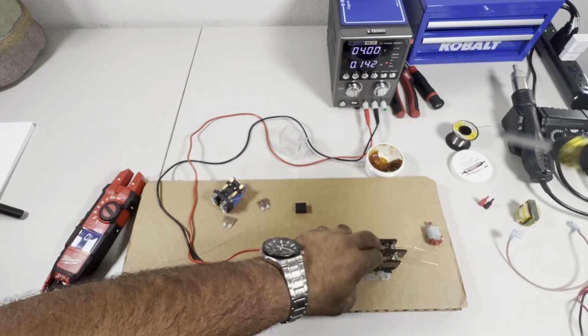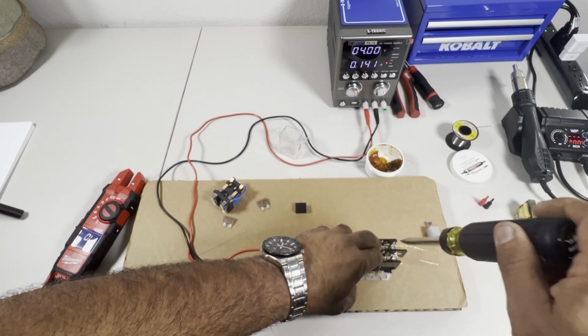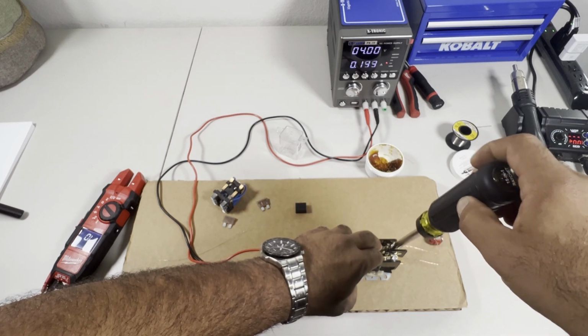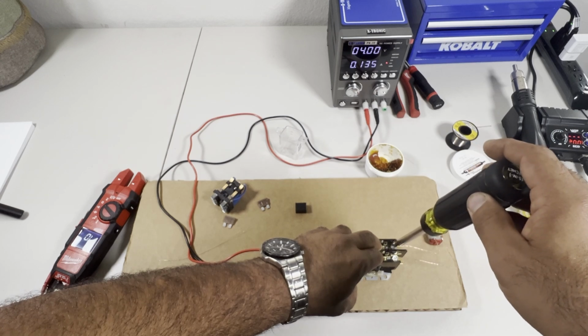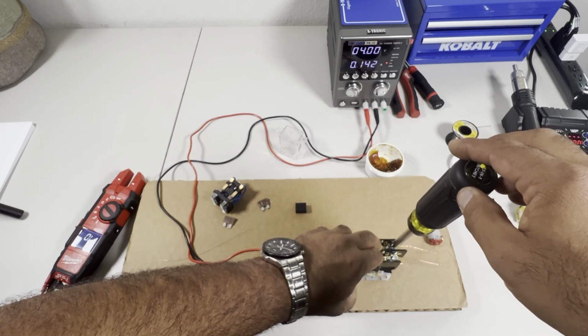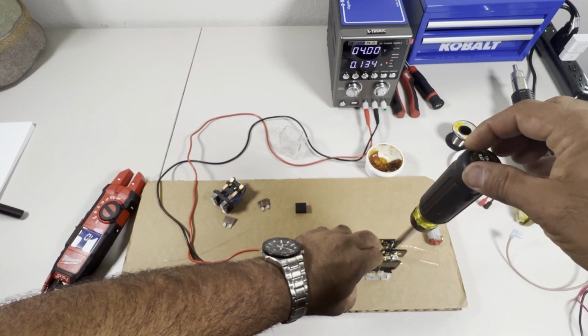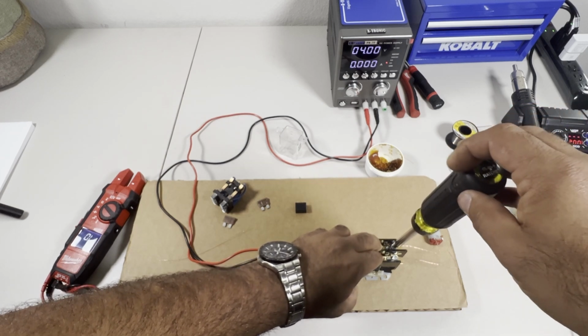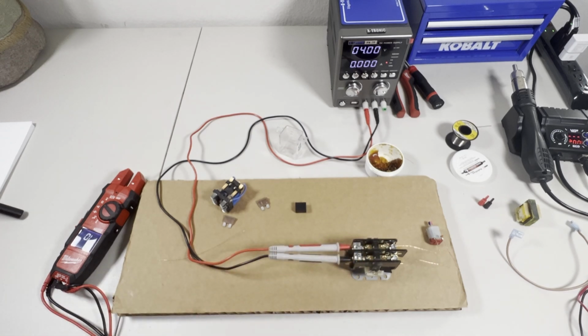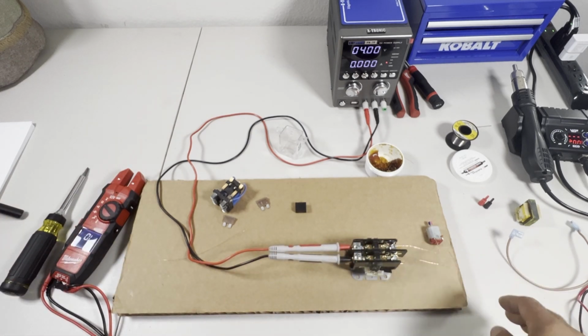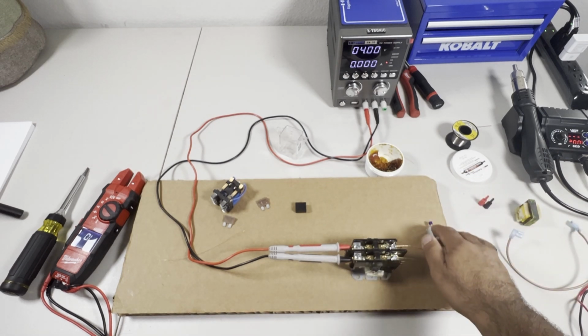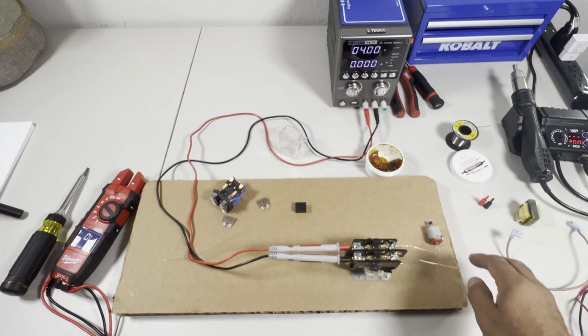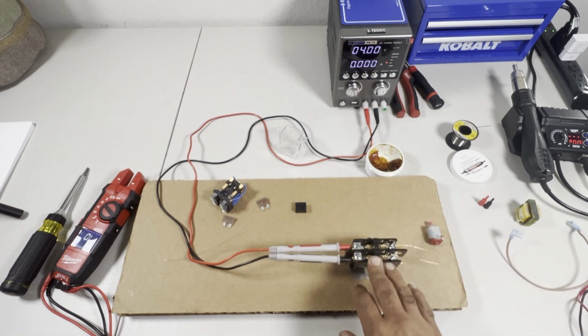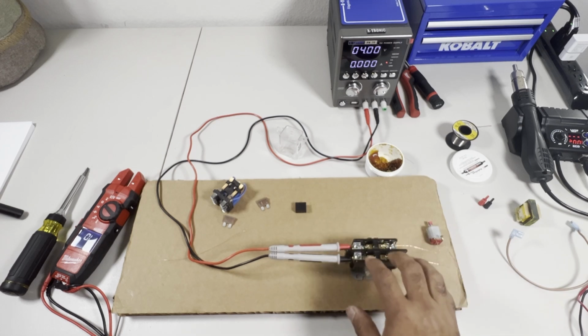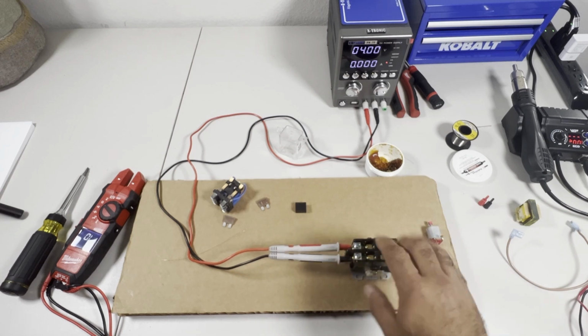The voltage is always going to be the same because it's coming from the generator. But your amperage is what is changing. The more arc you have, the more resistance is going to get added. Your motor is now struggling to run, and at one point, that's it, you're going to stop. But when that happens, since that motor is always under a load, you're putting a lot of pressure on the motor to run, especially when it's a compressor. That's an easy way to burn out the compressor. If there is a bad relay, with arced out or burned out points, always change it out.